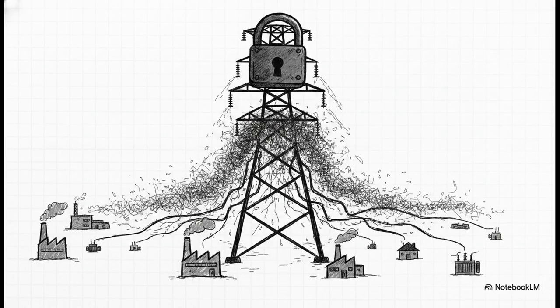Well, the logic is actually pretty brilliant. Electrical distortion is the most dangerous where it can travel the furthest and mess with the most connected equipment, and that happens at extra high voltage, the absolute backbone of the grid. If distortion runs rampant at 400 kilovolts, it's going to propagate across the entire network. So the regulatory leash absolutely has to be tightest at the top of the grid to protect everything downstream.